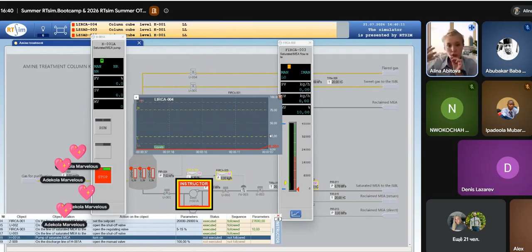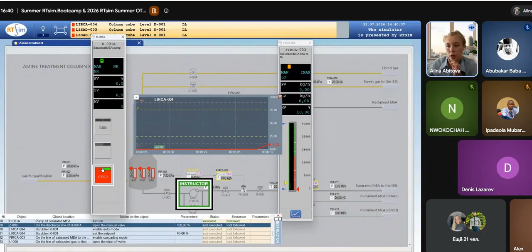In general, it will already let you open the pump as soon as it reaches the maximum emergency level. I guess it's something like 10% here. If you try to press the button to switch on the pump right now, it will turn on, as you can see, for a second, and after that turn off, because the emergency protection will be triggered. I will show you once again. So for example, look, we are opening the pump. The instructor is also showing that the action is followed and you did everything correct, but it's not like this because our pump is not working. The emergency protection simply turned it off.